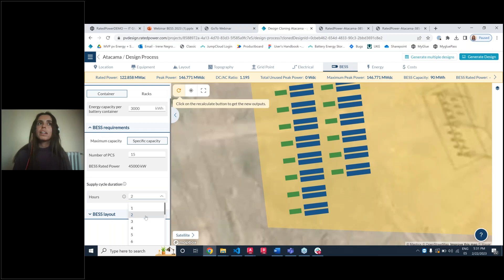It will depend a lot on where we are developing the battery system. Here in Spain, it could be 5% of the nominal or rated power of the PV plant, which would be a proper size for our battery system. So having, for example, a specific size of 122 megawatts AC installed in our plant, we can size our battery based on that, knowing we would like to install 5% of that nominal power. That would be a strategy for sizing our battery system. Inside the software, we just have to set the number of PCS, and that way we would be sizing our battery in terms of power.